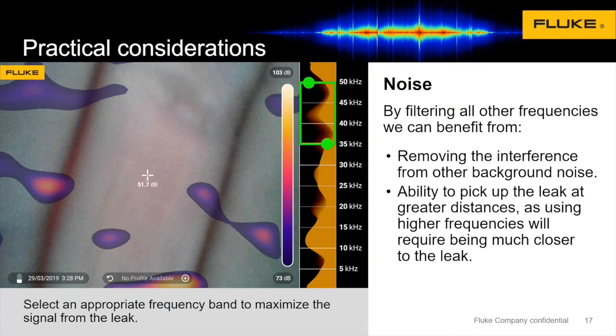What's on screen here is all just noise. In environments where you're getting a lot of noise, one way to eliminate that is by adjusting either the level or span of the frequency range you're visualizing sound within — either shrinking that range or moving it up and down. Another recommendation: once you've got a feel for the specific types of leaks you're looking for and what frequency range they happen within, getting a tighter band will allow the camera to be more sensitive. A really loose or wide band means some of those smaller leaks aren't going to be as easy to visualize.